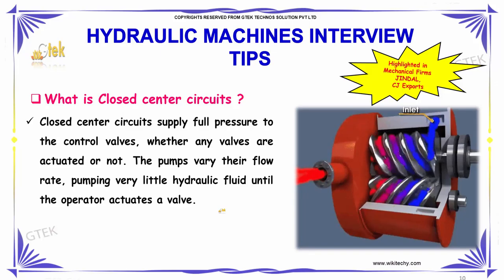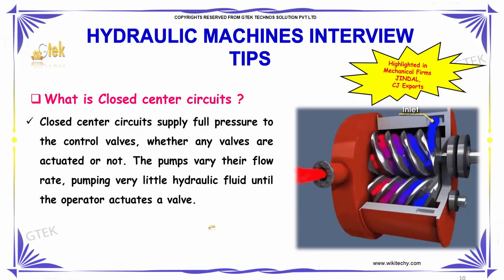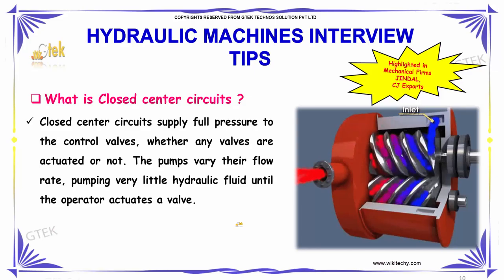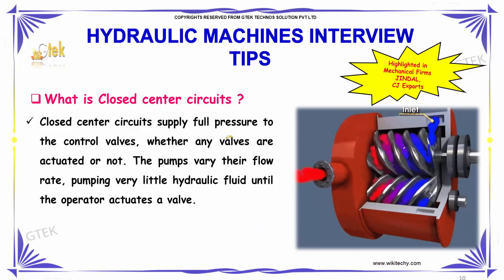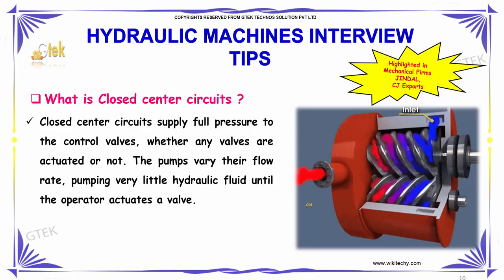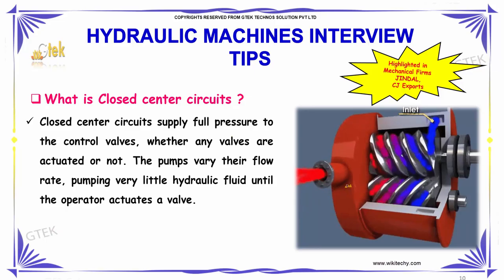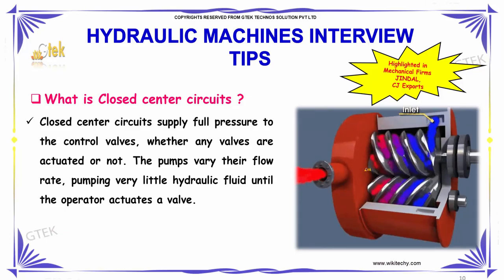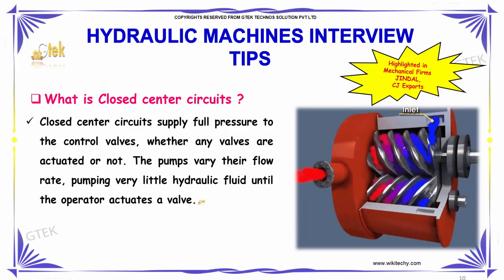What is meant by closed center circuits? In closed center circuits, supply full pressure to the control valve whether any valve is actuated or not. Once after that, the pumps vary their flow rate, pumping very little hydraulic fluid until the operator actuates a valve. This is the concept of closed center circuits.